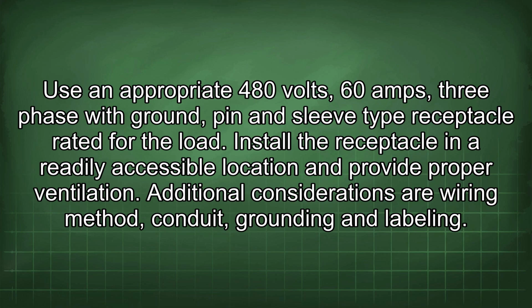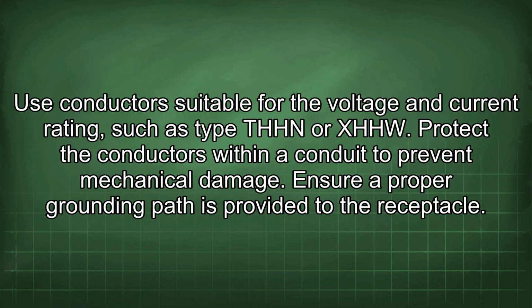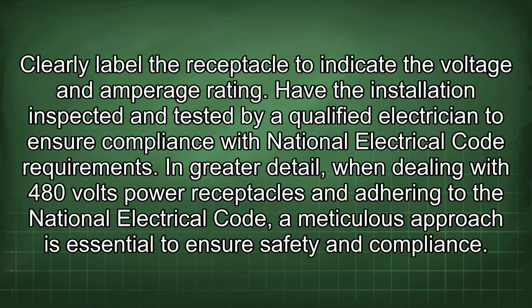Additional considerations are wiring method, conduit, grounding and labeling. Use conductor suitable for the voltage and current rating, such as type THHN or XHHW. Protect the conductors within a conduit to prevent mechanical damage. Ensure a proper grounding path is provided to the receptacle. Clearly label the receptacle to indicate the voltage and amperage rating. Have the installation inspected and tested by a qualified electrician to ensure compliance with National Electrical Code requirements.